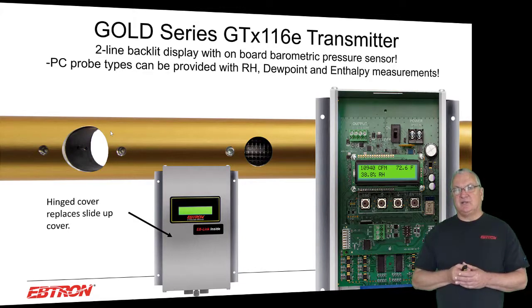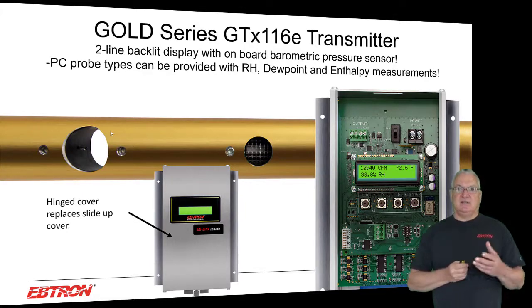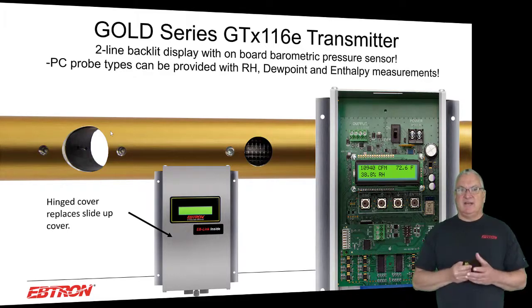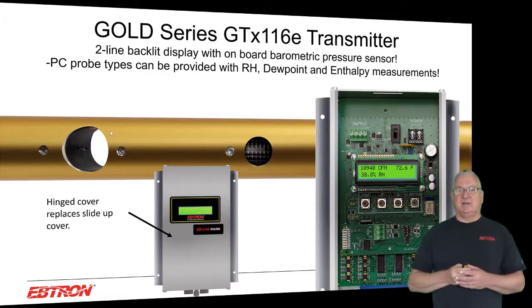When we take a look at the Gold series transmitter, again, this is kind of recent. We've gone to this GTX 116E or GTX 108E if it's the fan units. And it's this two-line backlit display. We've replaced our slide-up cover with a hinged cover. But on these probes, they're now available with a relative humidity sensor, which can provide you with weighted humidity, weighted enthalpy, or dew point, which is a big advantage. I think I see real opportunities there to use these products for economizer switchover. I also see reasons and advantages to use this product for supply air humidity control.